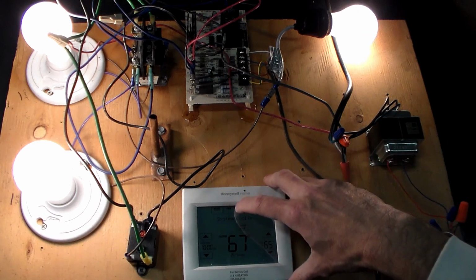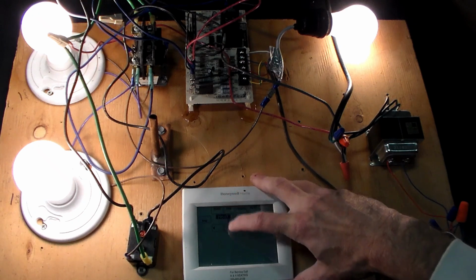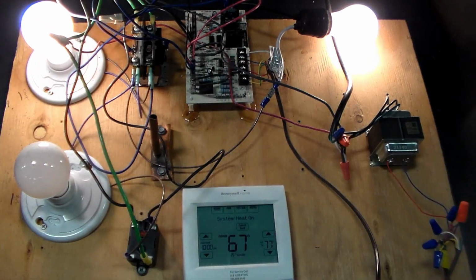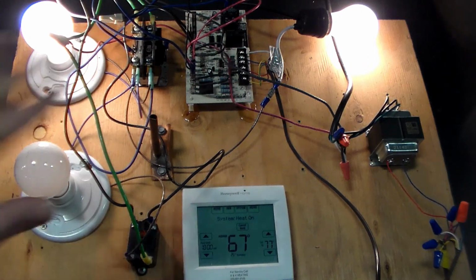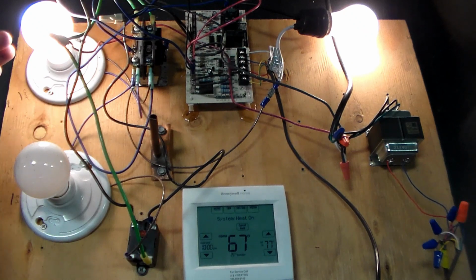When I go to heat, you can see that it cuts the reversing valve. So we're failing into heat mode. We're still going to run the compressor and the condenser fan, but we're going to cut that reversing valve now. We're in heat mode.